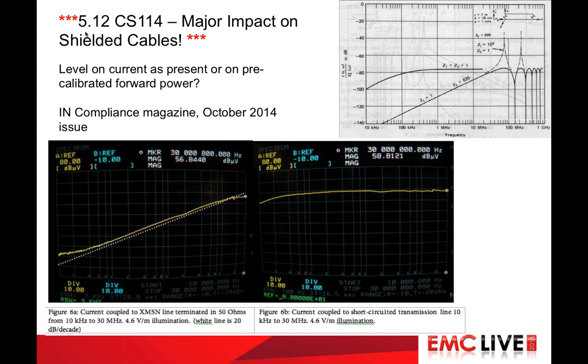In the plots above, the constant field intensity from 10 kilohertz to 30 megahertz illuminates a 1 meter long wire, which is 1/10 wavelength at 30 megahertz, so an electrically short wire over the entire frequency range. With 50 ohms at each end, the performance on the left is obtained, and one can see the near 20 dB per decade increase in coupled current, the superimposed dotted line, with noise floor at the low end and the beginning of transmission line effects at the high end providing the departure from the dotted line ideal. This represents the current to be established in the calibration fixture.